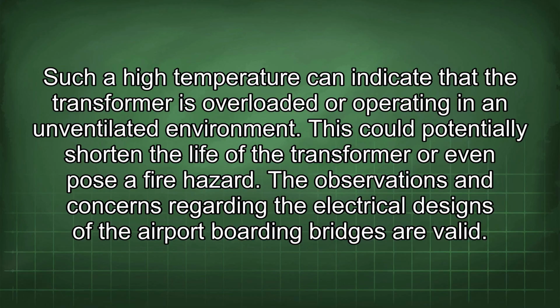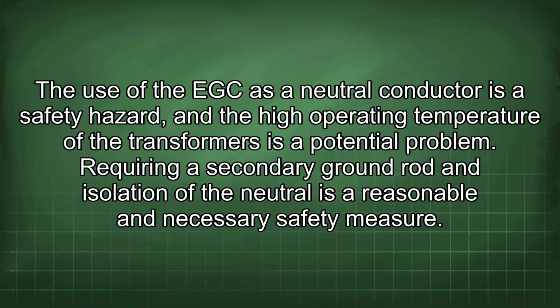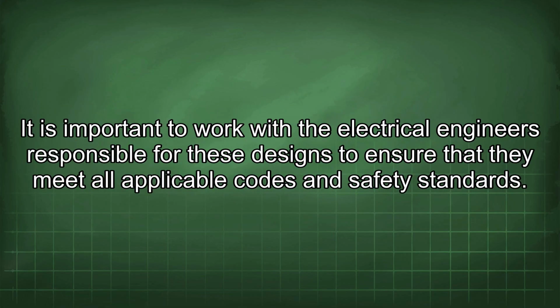The observations and concerns regarding the electrical designs of the airport boarding bridges are valid. The use of the EGC as a neutral conductor is a safety hazard, and the high operating temperature of the transformers is a potential problem. Requiring a secondary ground rod and isolation of the neutral is a reasonable and necessary safety measure. It is important to work with the electrical engineers responsible for these designs to ensure that they meet all applicable codes and safety standards.